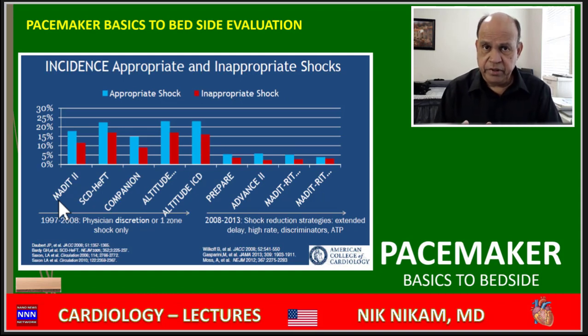Defibrillators built into these pacemakers are designed to deliver an electric shock. But there are times when the pacemaker may think the patient is having a serious arrhythmia and wants to deliver a shock, and it's not uncommon that the arrhythmia thought to be serious may not turn out to be serious. As a result, it may deliver an inappropriate shock.